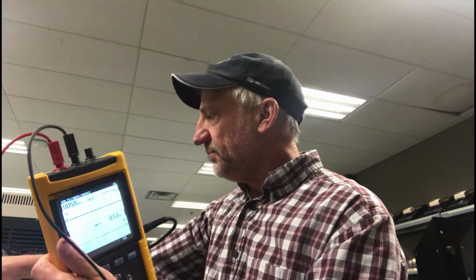Now once it's connected, look how far you need to push it down. It needs to be pushed down that far. If you just push it in a little bit, you won't get the proper connection for the current probe. So you can see I pushed it all the way down till it's flush there at the base. Then from there, you take the current probe lead and you push it down and twist to connect it. You'll know it's connected if you pull on it and it won't come apart. So you push down and twist, and the bayonet holds it in place. Okay, so now we've got our power analyzer set up properly for channel A and channel B, and now we just have to go in and make sure the instrument is set up properly for those test leads that are connected there.